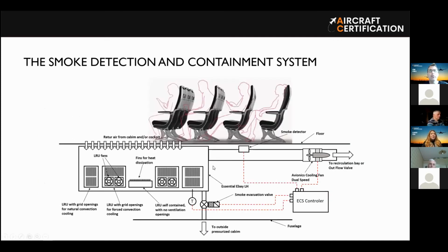So here are the same pictures, but this time, what's going to happen? Okay. So here we will have a smoke detector. You can see the smoke detector is in the outlet ducting. And provided that we have a smoke signal here, the ECS controller will send a warning signal to the pilot, and then the ECS controller will increase the speed of this fan, or will open this valve to throw the smoke outboard the aircraft. Okay.